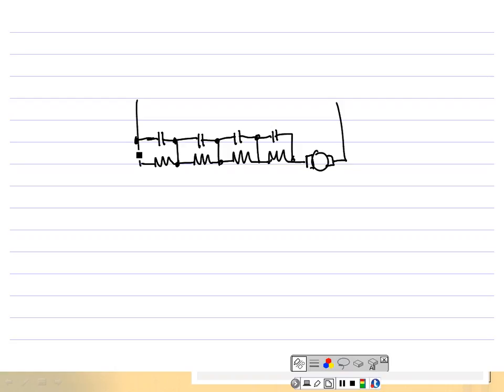This might be called speed 1, this might be speed 2, speed 3, and speed 4, and you'll see how this works. On your motor control you might have a joystick with 3 positions, or a selector switch: speed 1, speed 2, speed 3. The motor moves in speeds, and all you're doing is cutting out resistors by bringing in these contacts. This would be inside a control circuit.